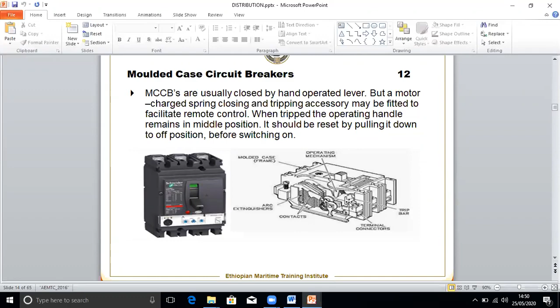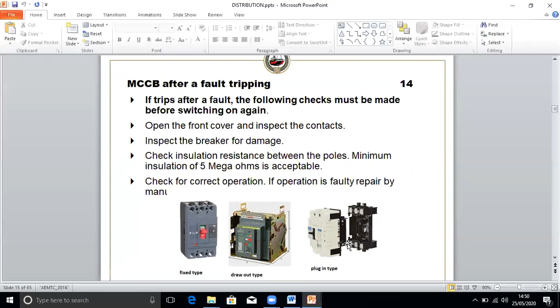If an MCCB trips after a fault, the following checks must be carried out. Open this front cover and inspect the breaker for damage. Check the insulation between the poles. Minimum insulation should be 5 megohms. Poles means this one, you see. This should be minimum 5 megohms. Check for correct operation. If it is faulty, repair it.